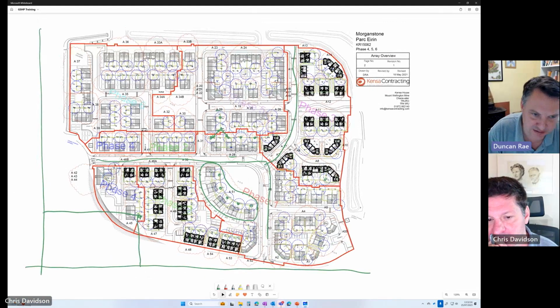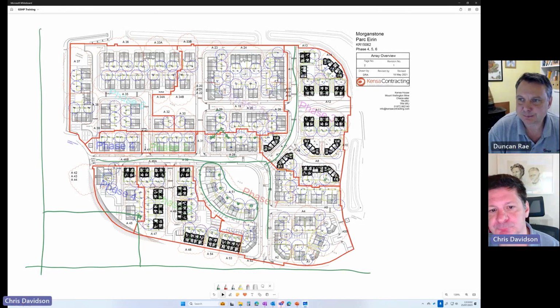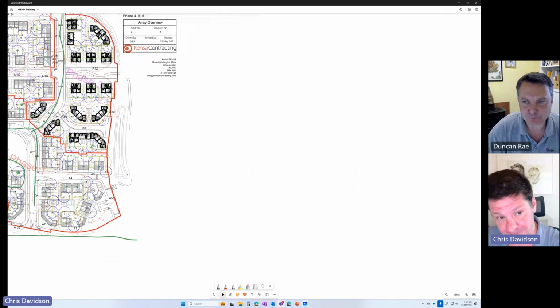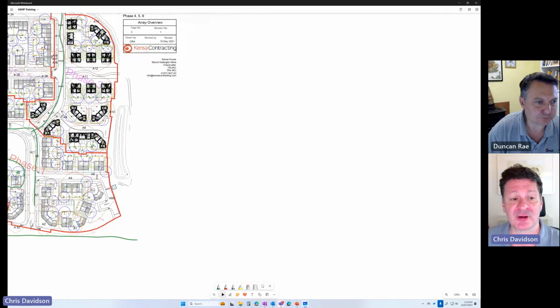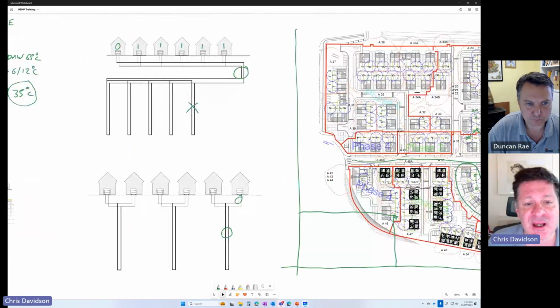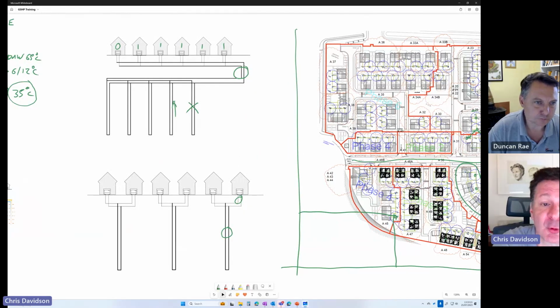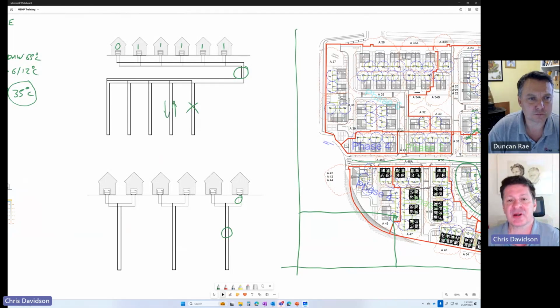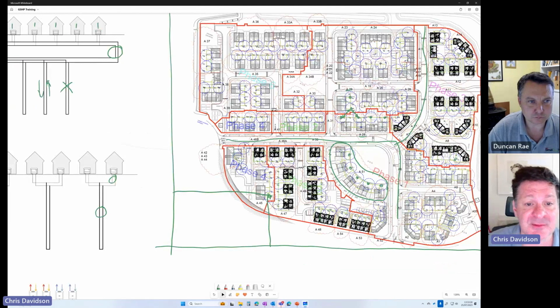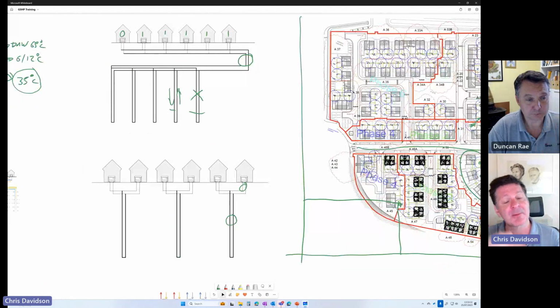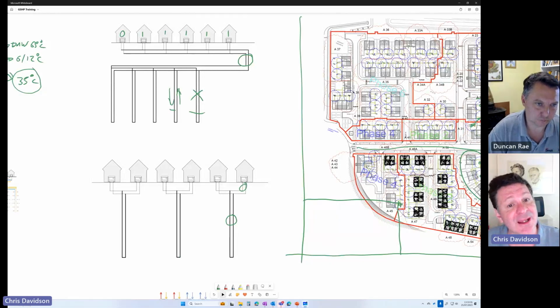Because in the real world, I doubt you can guarantee getting every borehole to exactly the same depth. Yeah, so there's a thing called pressure drop in systems. As you pump water around, one common misconception is that we're actually lifting the water up the borehole. But what comes up the borehole goes back down, so that's gravity-wise a neutral process. What we're doing in pumping is overcoming the frictional losses. It's called pressure drop in these systems. Now, if our boreholes are not the same depth, then because the longer the pipe, the higher the pressure drop, the longer boreholes are going to get less flow.